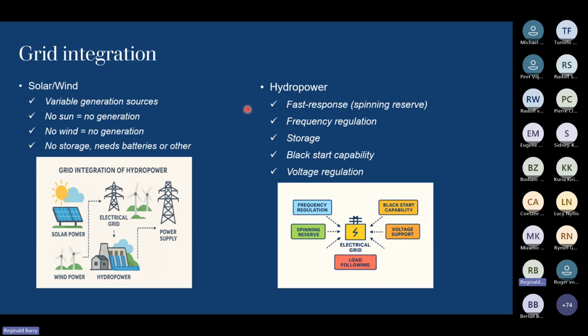Our pump storage schemes in South Africa - not sure about all of them, not sure about Steenbras, but the other two do - have black start capability, meaning that if for whatever reason we lose the grid completely, like what happened in Europe in parts of the grid, we can use these facilities to re-energize and start up the grid from scratch.